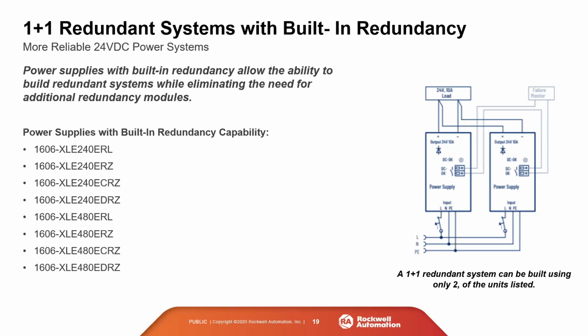These power supplies do come with two different connection terminal options to get the built-in redundancy. In the part number, if you see an L, that is for spring clamp terminals, and a Z would be for plug connector terminals. The plug connector terminals are the ones that are hot swappable that I mentioned earlier. So keep that in mind. And if you see a C, that's conformally coated. So we do offer some power supplies that have conformal coating. And then the D is an extra DC output for higher DC voltages.